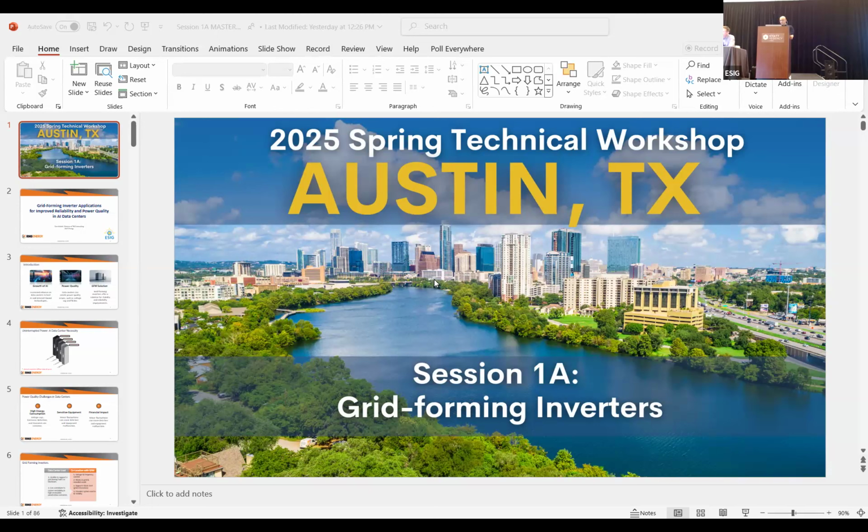What we found out is that grid forming is the solution. Grid forming technology can actually work perfectly here. It can reduce the flicker drastically. The first voltage that you see here is without grid forming. The second one is with grid forming, and you see that it's a good thing. And this is the final result. The flicker was so high that I don't think they could even connect to the grid, but if you pair it with grid forming technology, you can reduce the flicker drastically. And yes, there is an effect on the lifetime of the energy storage for sure, because of the speed of charge and discharge, but that's one of the solutions.